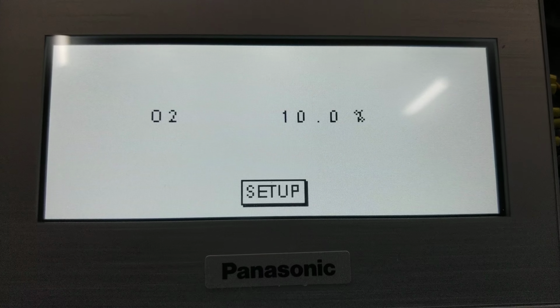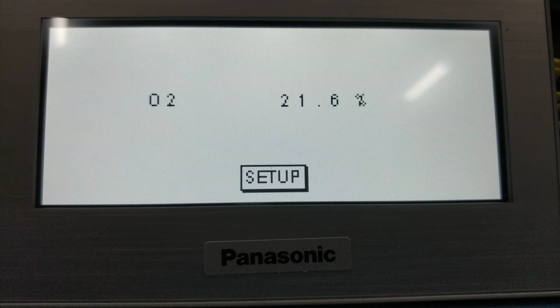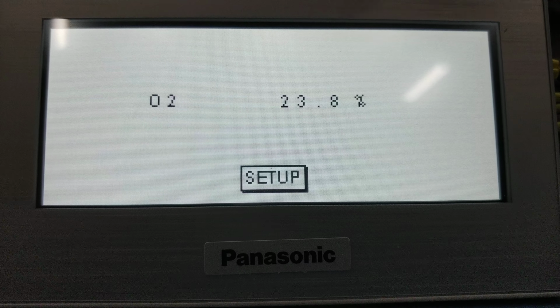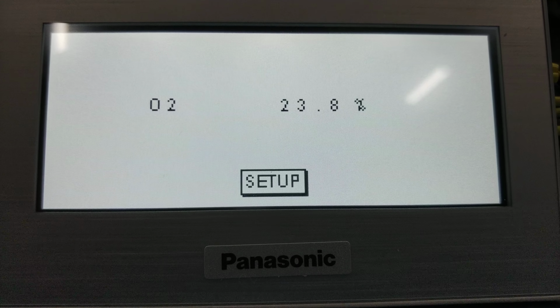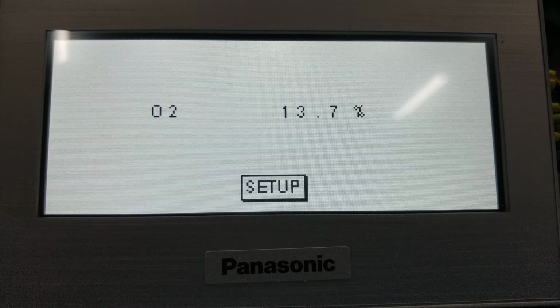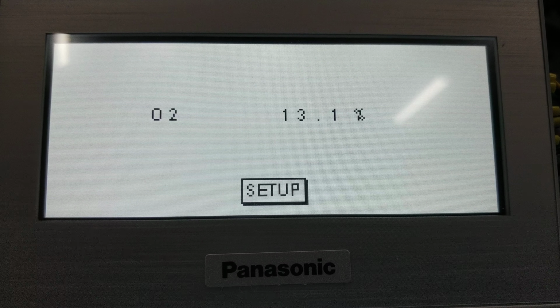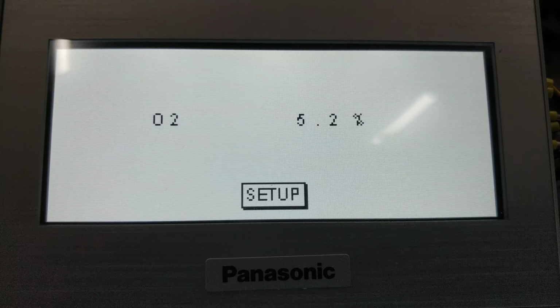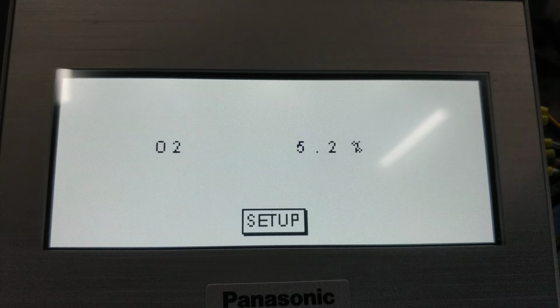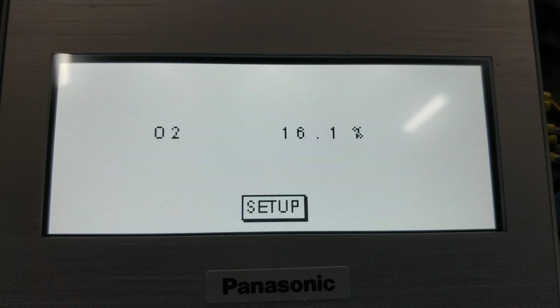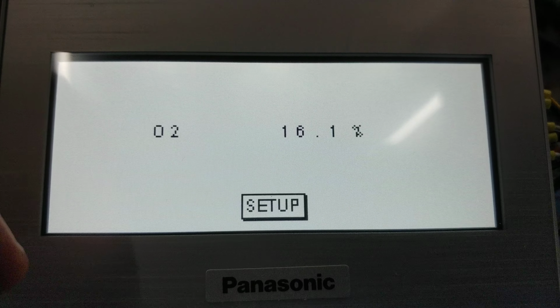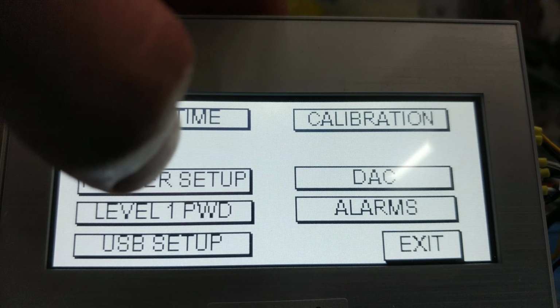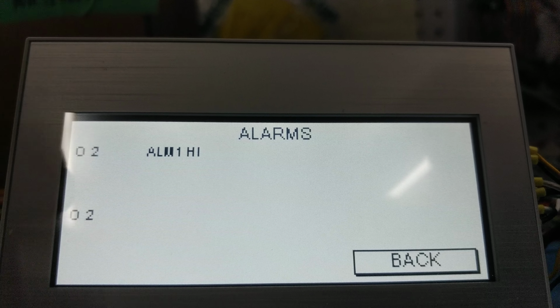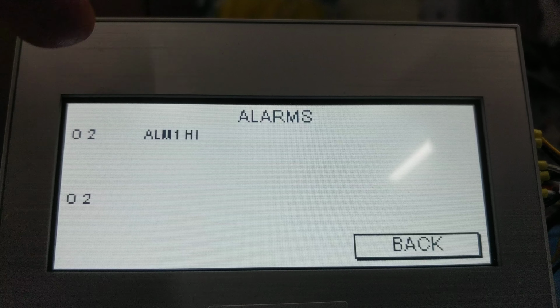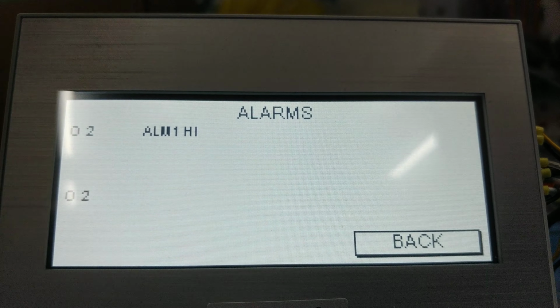Now let me see if I can simulate a gas alarm here. As you can see, I just simulated a high O2 reading and the alarm went on right away. I can bring it back down. So you see now the gas alarm is gone, and that's how you know the alarm is functioning, because the moment it goes above 12%, you're going to get an alarm reading. And you can check the alarms. You go to setup, alarms, and it tells you alarm 1 high. That right away tells you which alarm has happened. That's the high point, and that's pretty much it.